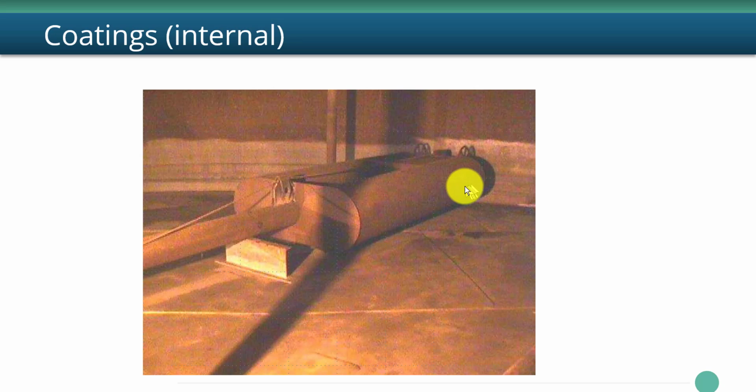There's always water dropping out of almost every petroleum storage tank because of the solubility of water in the organic liquid. Yes, it's soluble just like water vapor is soluble in the air, and if the conditions change, it will drop out and create a fog or a cloud and rain. The same thing happens in petroleum liquids.